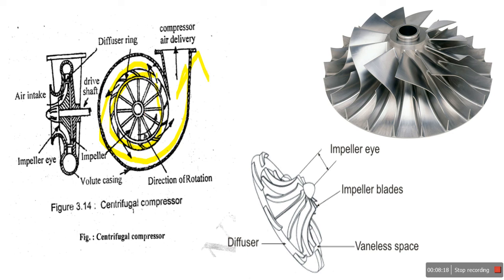To repeat the working: a centrifugal compressor consists of a rotating member known as the impeller, which has a number of blades and is mounted on the compressor shaft inside a stationary volute casing. As the impeller rotates, the pressure at the center region falls and air enters the eye of the impeller — air actually enters due to centrifugal force.